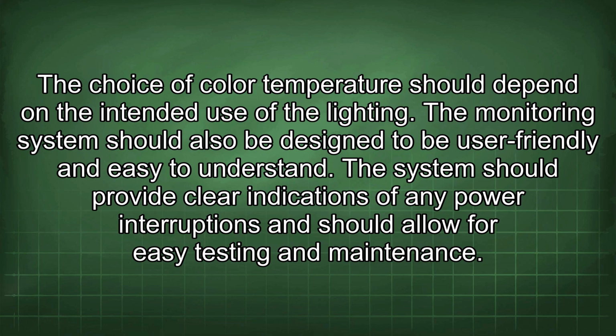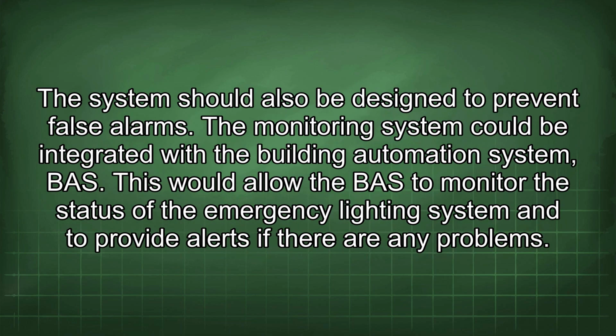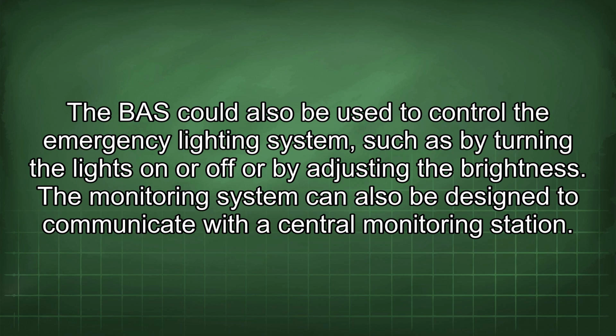The monitoring system should also be designed to be user-friendly and easy to understand. The system should provide clear indications of any power interruptions and should allow for easy testing and maintenance. The system should also be designed to prevent false alarms. The monitoring system could be integrated with the Building Automation System (BAS). This would allow the BAS to monitor the status of the emergency lighting system and to provide alerts if there are any problems. The BAS could also be used to control the emergency lighting system, such as by turning the lights on or off or by adjusting the brightness.